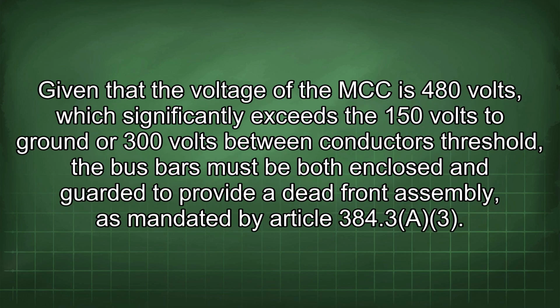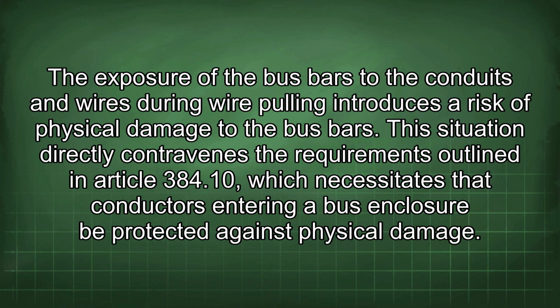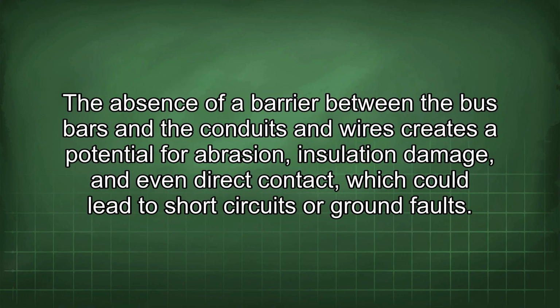Given that the voltage of the MCC is 480 volts, which significantly exceeds the 150 volts to ground or 300 volts between conductors threshold, the bus bars must be both enclosed and guarded to provide a dead front assembly, as mandated by Article 384.3A3. The exposure of the bus bars to the conduits and wires during wire pulling introduces a risk of physical damage to the bus bars. This situation directly contravenes the requirements outlined in Article 384.10, which necessitates that conductors entering a bus enclosure be protected against physical damage. The absence of a barrier between the bus bars and the conduits and wires creates a potential for abrasion, insulation damage, and even direct contact, which could lead to short circuits or ground faults.